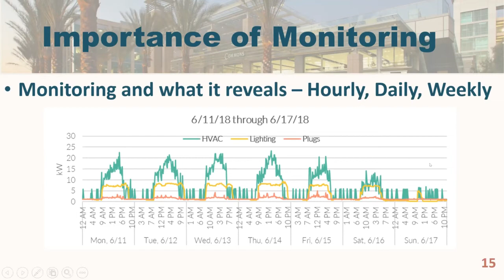This is an example from a library for the county. There was a wildfire nearby that knocked out the power, and it erased the schedule in the VRF system controller. So on Friday, August 17th, in the middle of the day, the VRF system started running 24/7. If we were only using utility data to track the zero net energy performance of this building, we may not have known about this for a long time. But because we have this kind of interval data and can look at it anytime, it was identified early — and especially on a zero net energy building, you don't want this kind of activity going on, or you'll jeopardize your zero net energy goal.